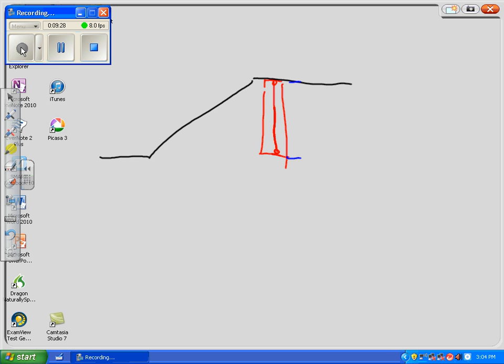And then, for instance, if you're using a 30-degree kick, meaning this angle right here is only 30 degrees, and you can see in this case, it doesn't, not that one. I've just drawn the wrong angle. Sorry. Let me fix this real quick. And if this angle is only 30 degrees, then we can just double this distance.